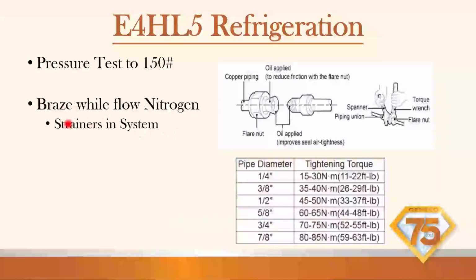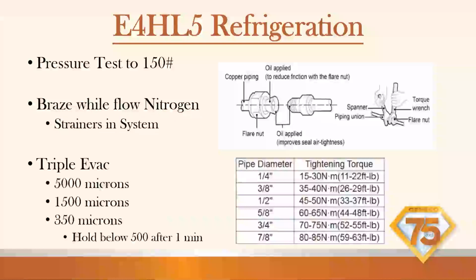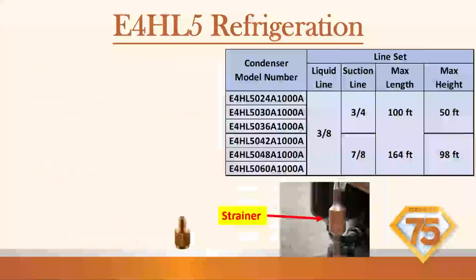Braze while flowing nitrogen. So you're always going to flow nitrogen. Strainers in the system, I'll show you those. We always want to run a good triple evac. Get it down to 350 microns, and then close the system. And if it states it's got to hold below 500 after a minute, you've got a good evacuated or pumped down system.